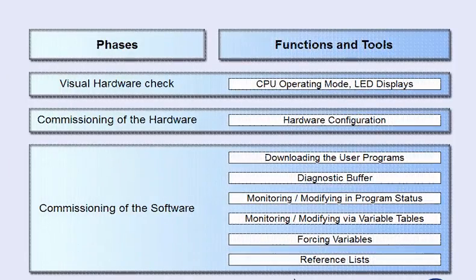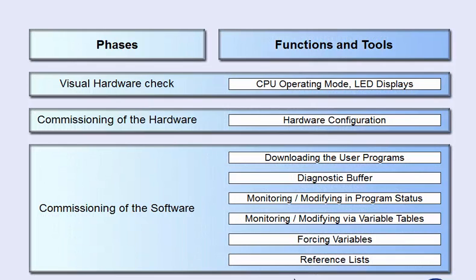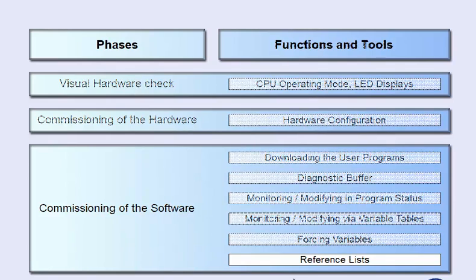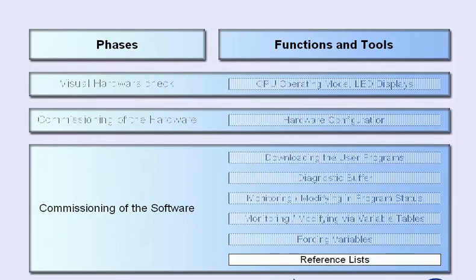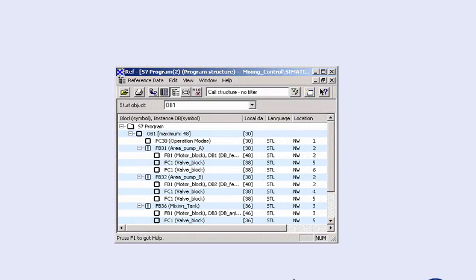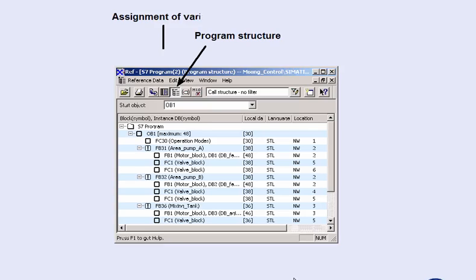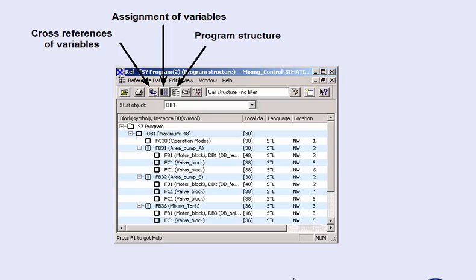In large software projects, it is often difficult to keep track of the complex program structure or the numbers of used variables. The Simatic Manager supports you in this with the option of generating reference lists. On demand, the Simatic Manager compiles the desired overview compactly in the form of lists. The reference data most important in practice are program structure, assignment of variables and cross-references of variables. The display of this data can be defined individually by means of filter settings.